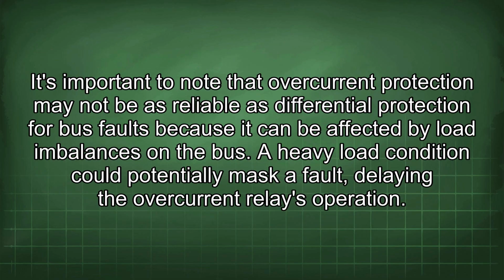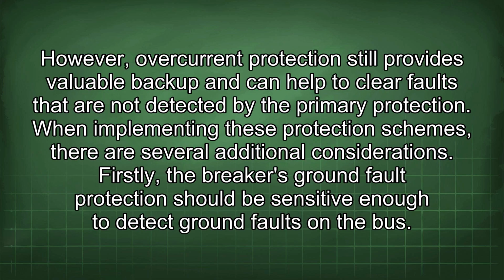It's important to note that overcurrent protection may not be as reliable as differential protection for bus faults because it can be affected by load imbalances on the bus. A heavy load condition could potentially mask a fault, delaying the overcurrent relay's operation. However, overcurrent protection still provides valuable backup and can help to clear faults that are not detected by the primary protection. When implementing these protection schemes, there are several additional considerations.